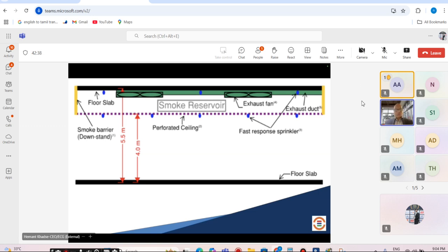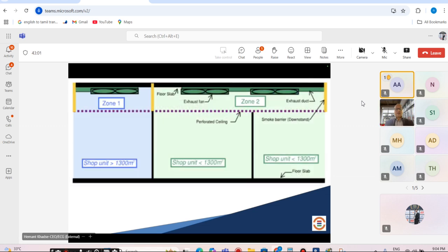So when you design these smoke zones, you have to use an engineered way and see how your mechanical ventilation is going to be engineered so that your area becomes smoke-separated zones and they are coordinated. When you look at all the applications, as I mentioned, you have all the flexibility and applications given in the standard. That means you can define your strategy in your report or in your design basis at the design level, so that the integrated systems can be established. As I mentioned, your sprinkler system is going to exist and operate in a fire, and so will your smoke extraction system, and so will your pressurization systems.